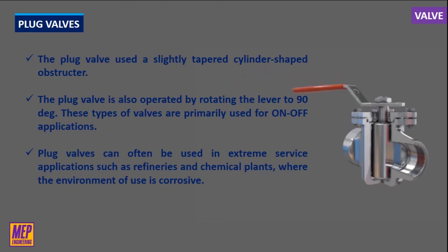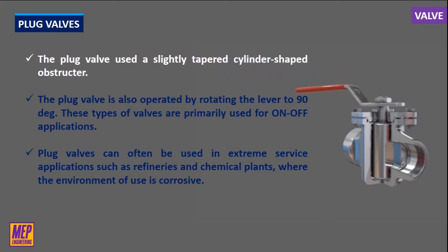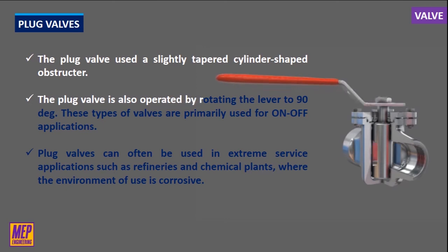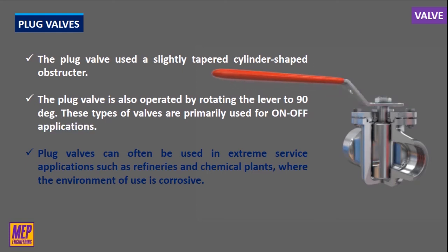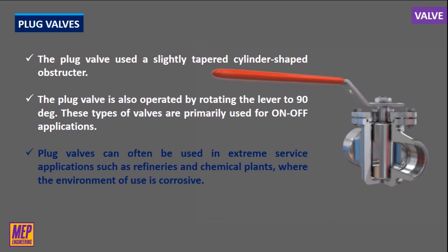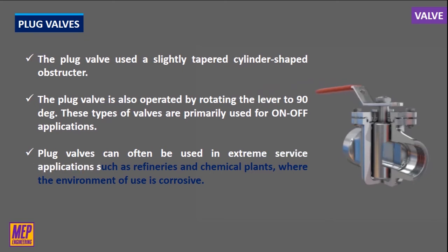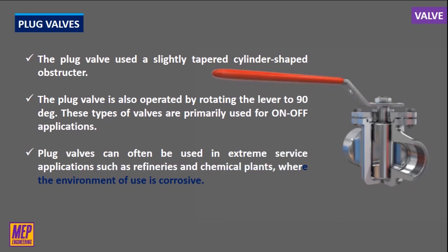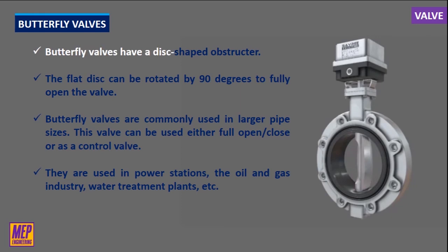The torque required to operate a ball valve is negligible. Plug valves have almost the same construction as ball valves, except for the shape of the obstructor — the plug valve uses a slightly tapered cylinder-shaped obstructor. The plug valve is also operated by rotating the lever 90 degrees. These types of valves are primarily used for on-off applications. Plug valves have an advantage over ball valves in that they contain no voids or cavities in which media can get trapped. They can be adjusted to fix leaks that develop over time and can be used in extreme service applications such as refineries and chemical plants where the environment is corrosive.